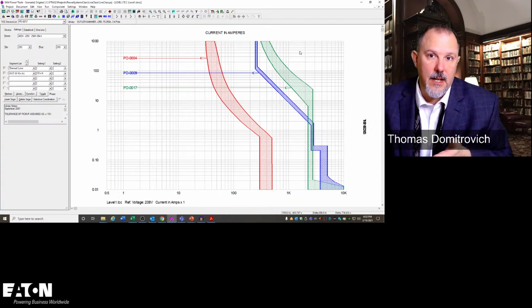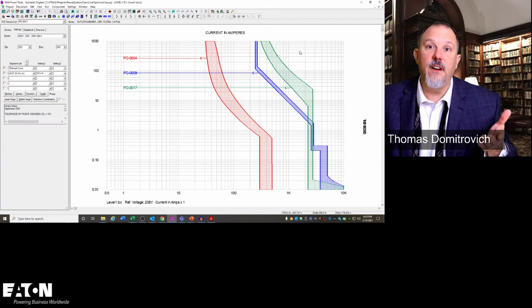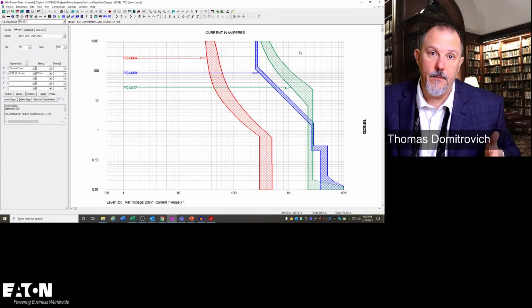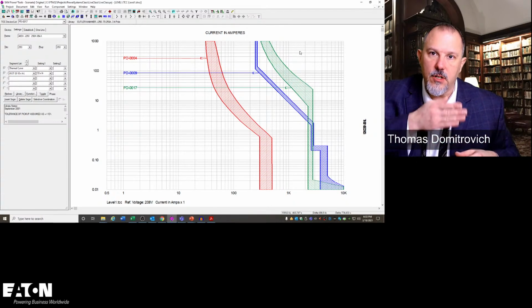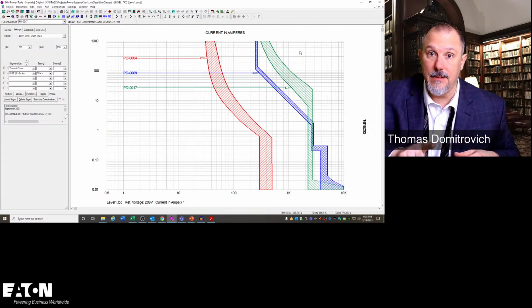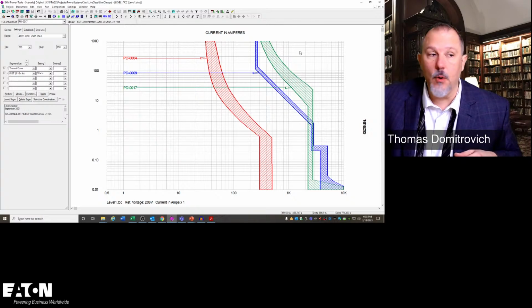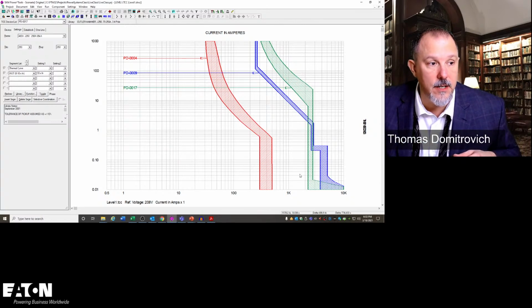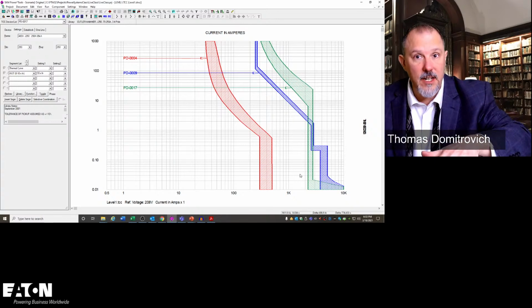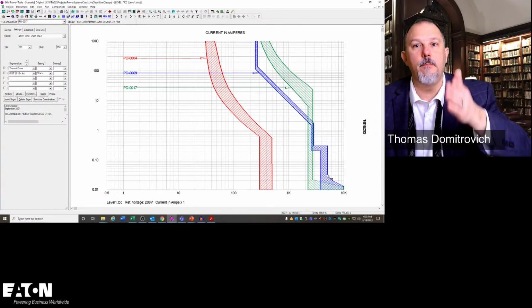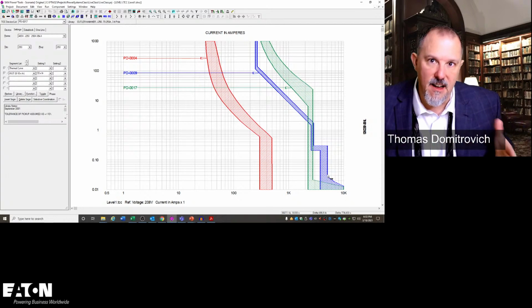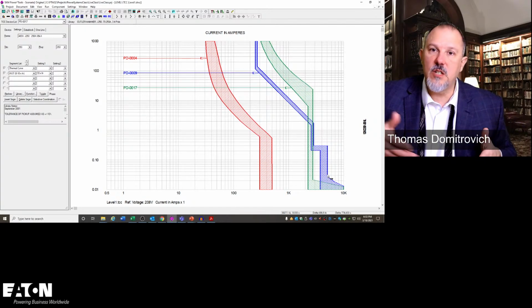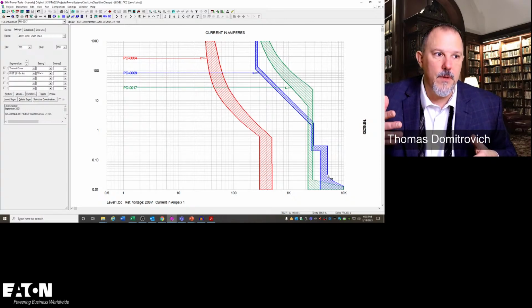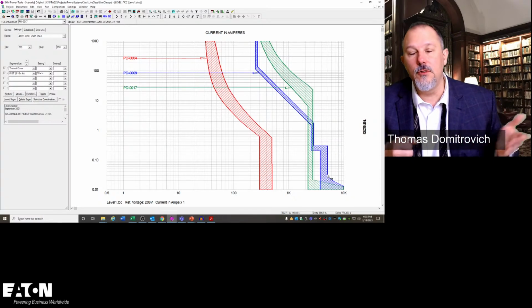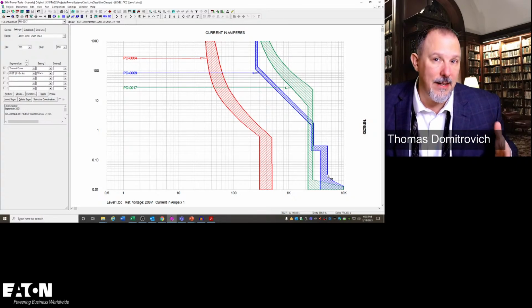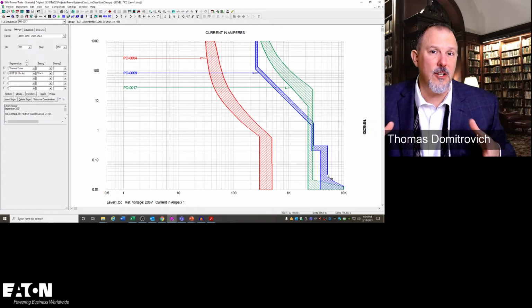So if I'm selectively coordinating to that, then I have 100% assurance that I'm never going to have a cascading event. The moment you start coordinating to lower values of fault current, now you are making some guesses, right? I could use 1584, calculate the arcing ground fault current and plot that and say, look, you selectively coordinate to the arcing fault current. You don't selectively coordinate to the bolted fault current, but based upon your application, that might be enough. That might be the sweet spot. It's not a life safety system. If I lose some coordination because I had a higher fault current than what I anticipated, and I took a little bit more of my system out, I'm not going to lose sleep over it.